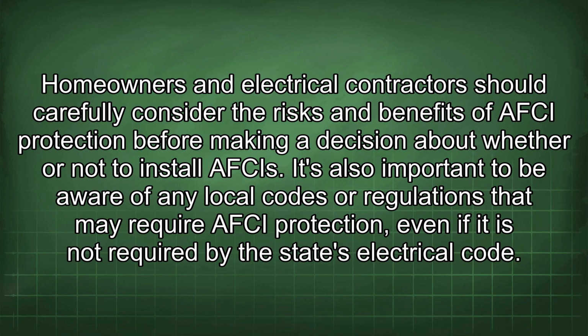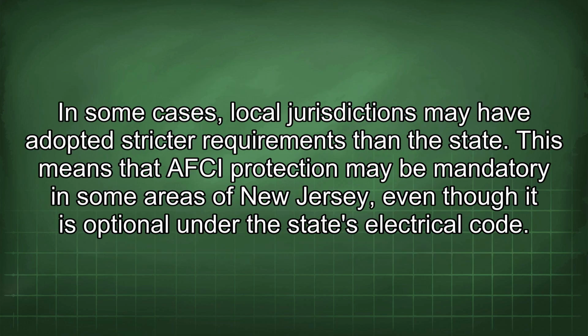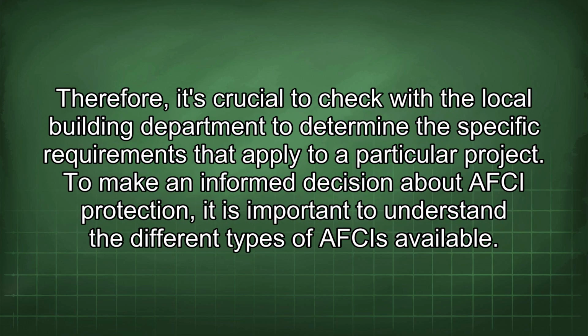It's also important to be aware of any local codes or regulations that may require AFCI protection, even if it is not required by the state electrical code. In some cases, local jurisdictions may have adopted stricter requirements than the state. This means that AFCI protection may be mandatory in some areas of New Jersey, even though it is optional under the state's electrical code. Therefore, it's crucial to check with the local building department to determine the specific requirements that apply to a particular project.